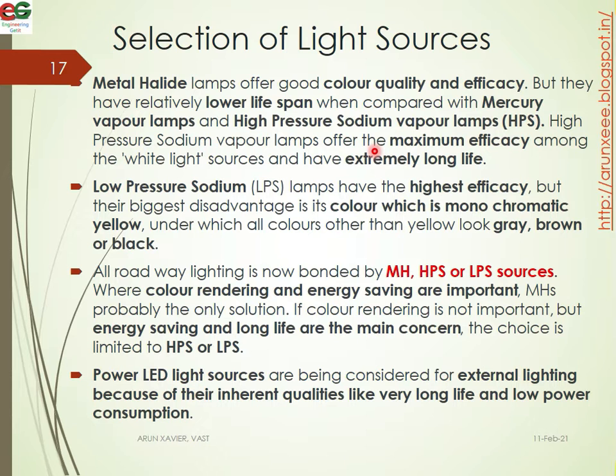Low Pressure Sodium type of lamps are available and have the highest efficiency. However, the disadvantage is that the color is monochromatic — colors such as brown or black can look dark or grey under Low Pressure Sodium Vapor lamps.